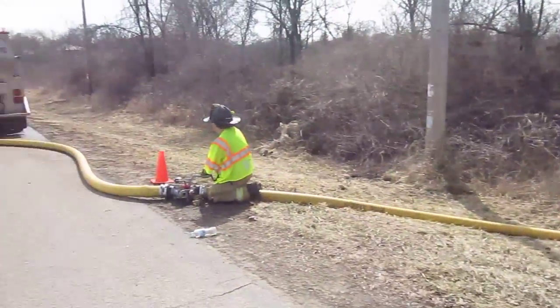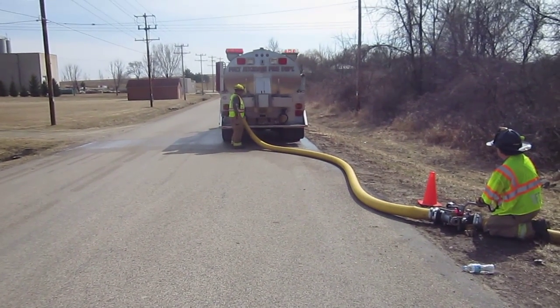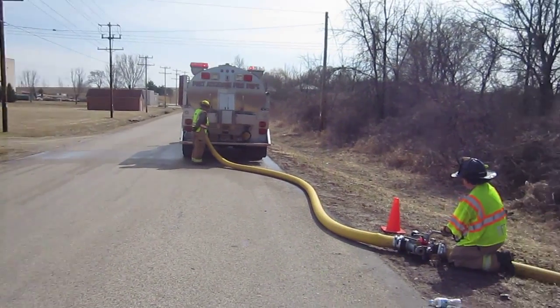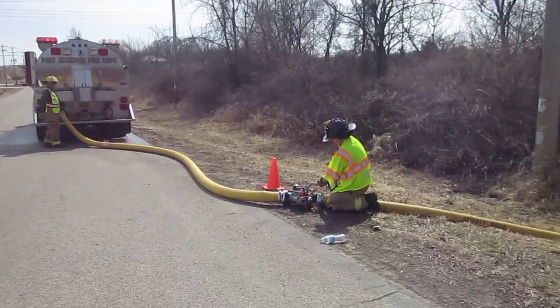Good job there filling these tenders somewhere in the neighborhood of about 1,200 to 1,500 gallons a minute. And as we said, our fire flow is at 1,750 gallons a minute. This round trip is just in the neighborhood of about 2 miles, we believe.